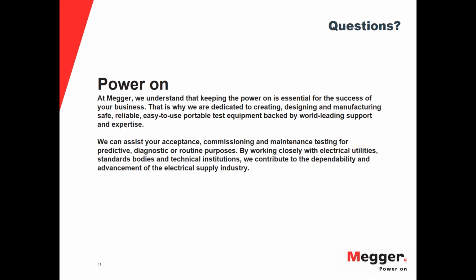Do not go beyond the minimum voltage or the end voltage. And by following the testing schedule that we mentioned, every 25% at least, you're not testing the battery so often that you're going to be taking too many cycles. So in the end, it's like any other test in the electrical world: if you don't use it correctly, you can destroy the equipment. But if you use it correctly, it's going to be a safe test and it's not going to affect your battery. All right, the next question.